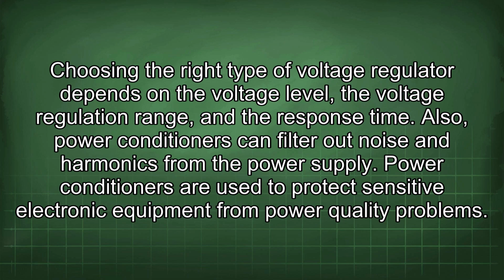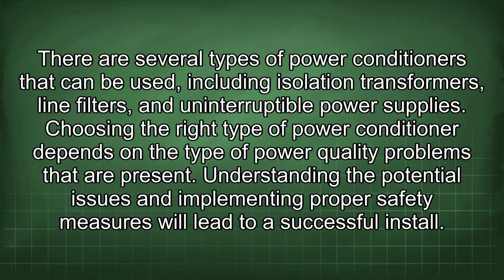Also, power conditioners can filter out noise and harmonics from the power supply. Power conditioners are used to protect sensitive electronic equipment from power quality problems. There are several types of power conditioners that could be used, including isolation transformers, line filters, and uninterruptible power supplies. Choosing the right type of power conditioner depends on the type of power quality problems that are present. Understanding the potential issues and implementing proper safety measures will lead to a successful install.